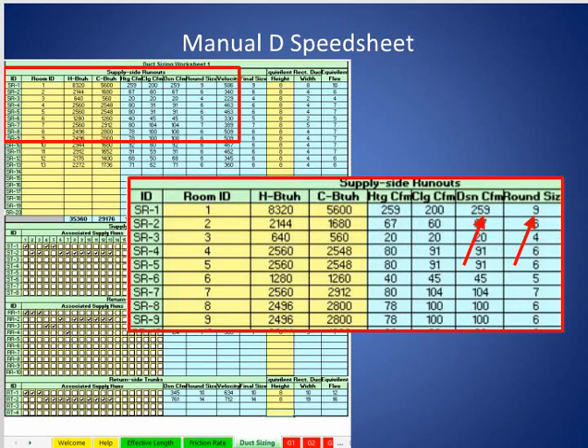We get a design CFM of 259. That's not to be confused with the air flow used later when we do balancing. This design CFM is strictly for duct sizing. If we ever tried to use this design CFM for balancing, we'd never balance the system — because we've picked the larger number between heating and cooling CFM all the way down this column. Some are on the cooling side and some on the heating side. The air handler won't put out the total CFM if you add up the design CFM column. However, in order to have ducts big enough to handle the air without restriction, we need to use the design CFM — so this is for duct sizing only.